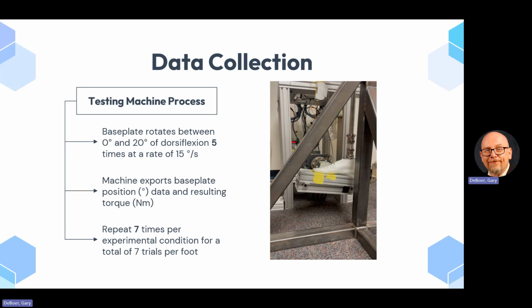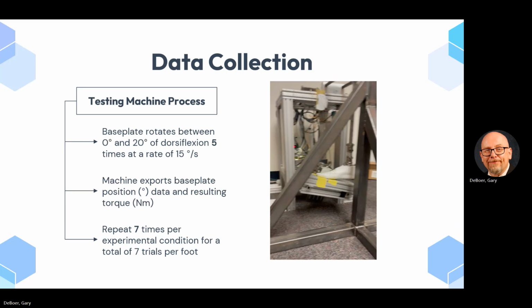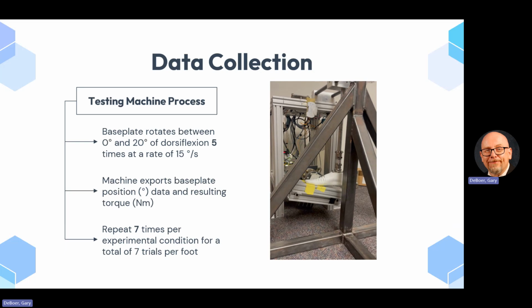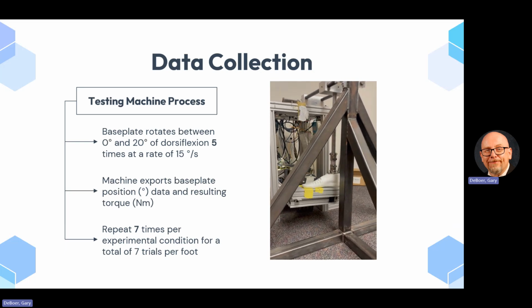For data collection, the base plate of the testing machine rotates from a neutral position, which is 0 degrees, to 20 degrees of dorsiflexion and then back to that neutral position. And this rotation will occur 5 times at a rate of 15 degrees per second, mimicking normal gait. And the machine captures the base plate position in degrees and the resulting torque in newton meters. And each foot will undergo 7 different trials. Oh, you can see this is what we're doing. So it'll go 7 times.